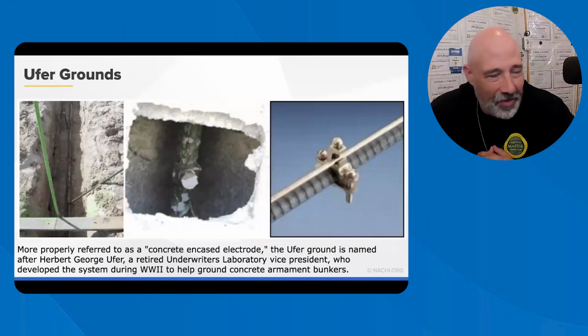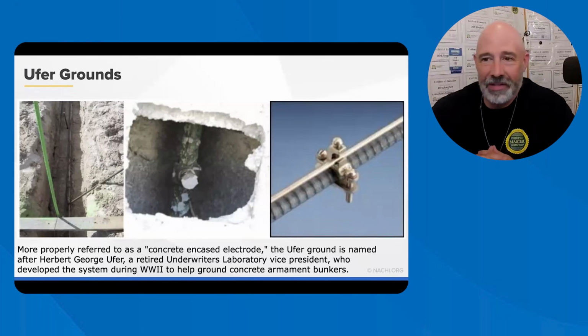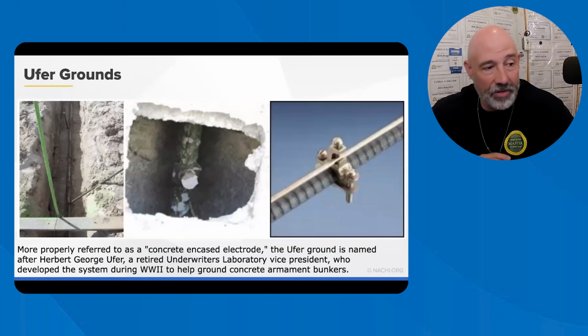So with so many homes and commercial buildings now built on concrete, steel reinforced slabs, this grounding system has become very popular. The requirements for the Ufer ground are that they have either 20 feet of number 4 rebar or a 4 AWG copper wire embedded into at least 2 inches of concrete, which is within the footer and so on and so forth.